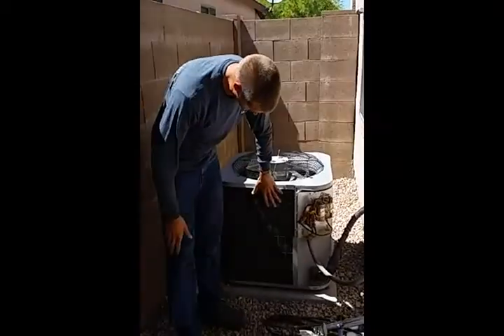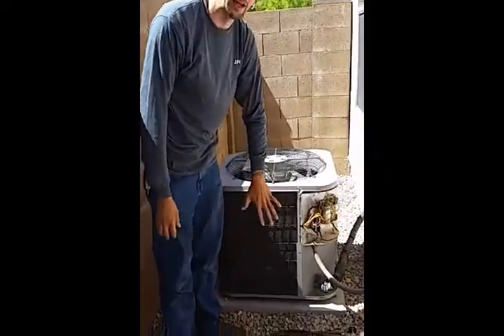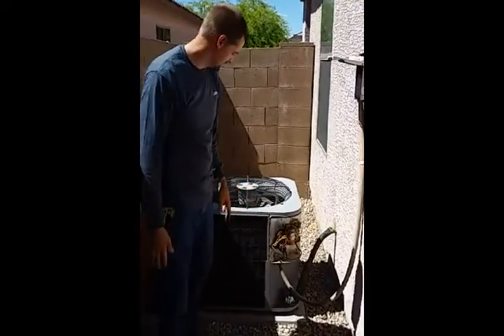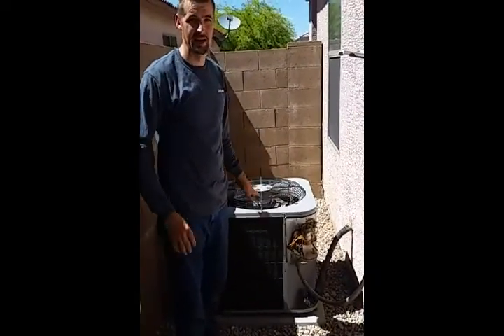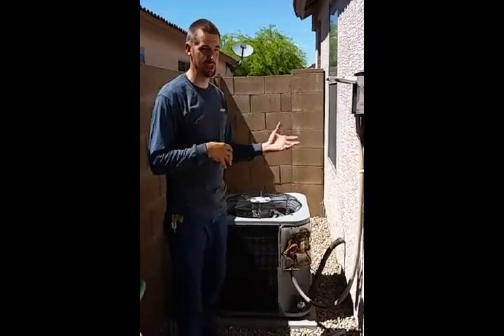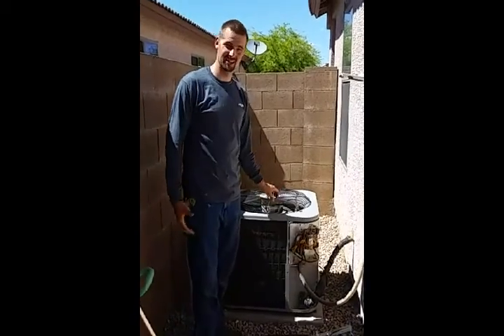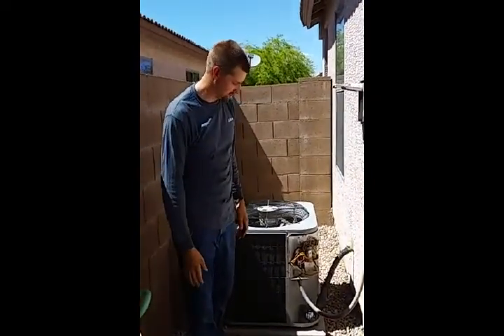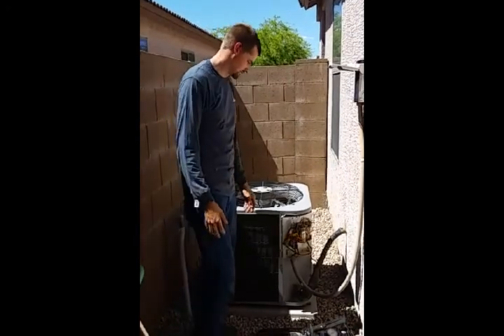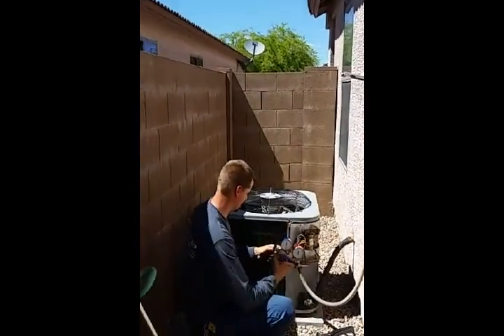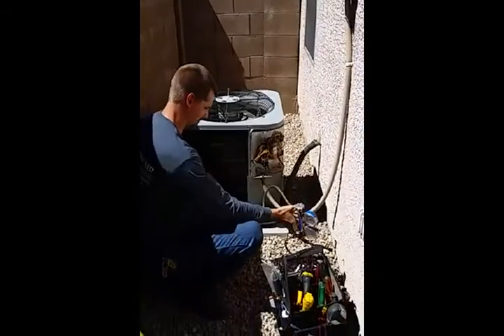And another thing I want to go over is every time I do a system checkout, it includes a coil cleaning. And then it does include a brief inspection of the indoor coil. Sometimes you can't get to the indoor coil as easily, so you either have to A, pump down all the Freon into the condenser, then cut the lines and pull it out and clean it, or B, we can pull off the return sometimes and get in and clean it that way. It just really all depends on what kind of system you have, the application, is it in a closet, in an attic, those kind of things. So we'll go ahead and put on our gauges here.